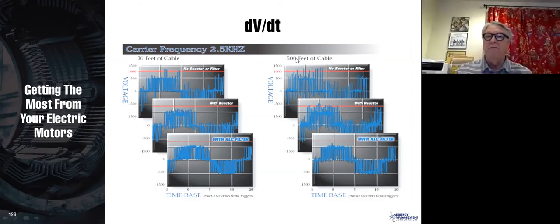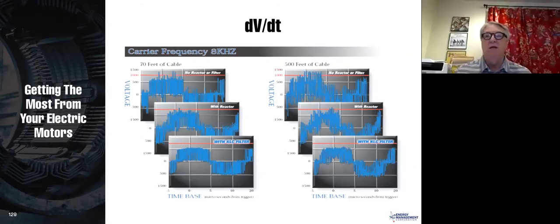Now over here we have 500 feet of cable, and the longer cable allows for higher spikes, and you can see those spikes are getting increasingly over 1000 volts. You certainly wouldn't want to use this on a standard motor in a situation like this. Now notice the carrier frequency is 2.5 kilohertz. That's the frequency of the pulses. If we change that carrier frequency to 8 kilohertz, things get much worse. So I think you can see why we want to use a motor with the high spike wire that meets NEMA MG1 Part 31 anytime we're going to put a motor on a variable frequency drive.